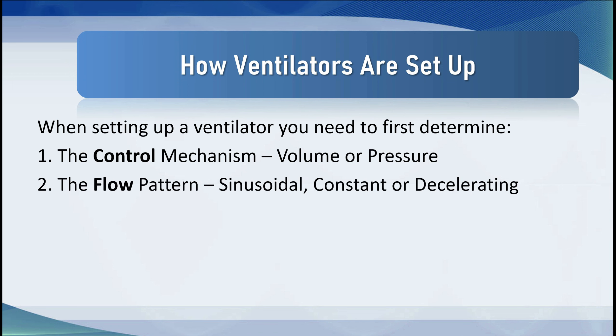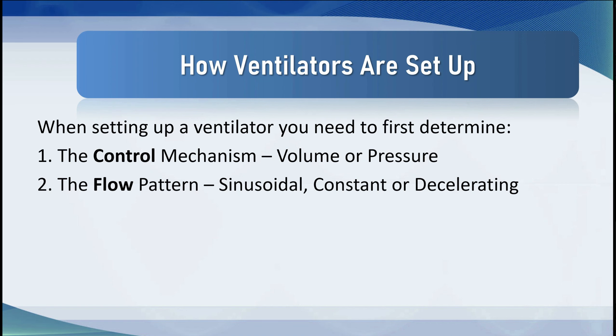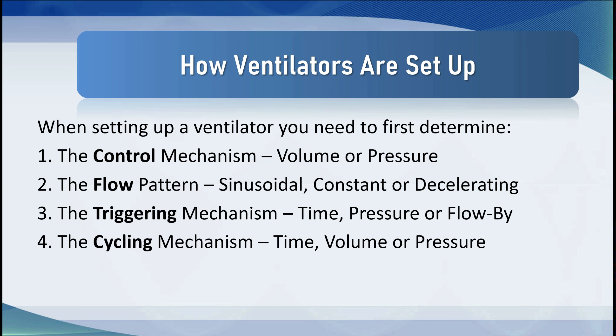We also need to determine the flow pattern — sinusoidal (which looks like a sine wave), constant, or decelerating — the triggering mechanism, which is how the ventilator knows when to give a breath. That can be time trigger, pressure trigger, or flow-by trigger. And finally, the cycling mechanism — how the ventilator goes from inspiration to exhalation — which can be time, volume, or in some cases pressure.